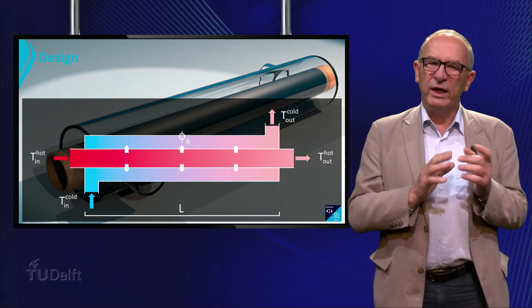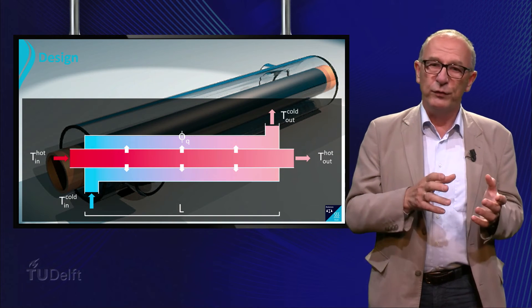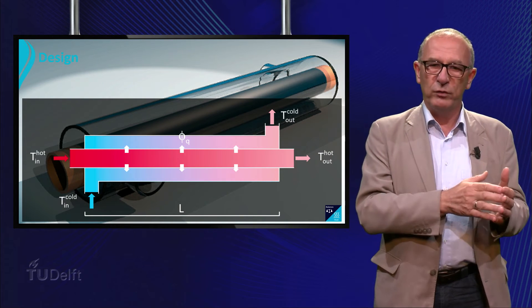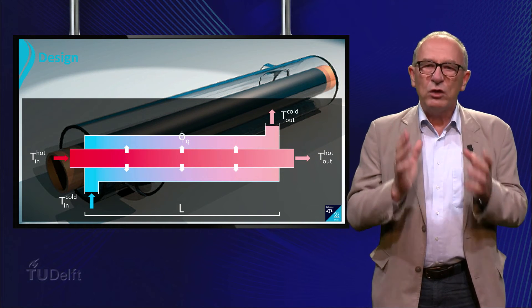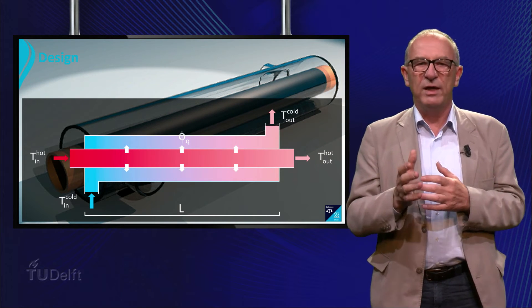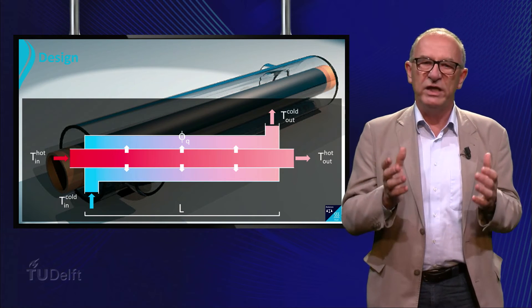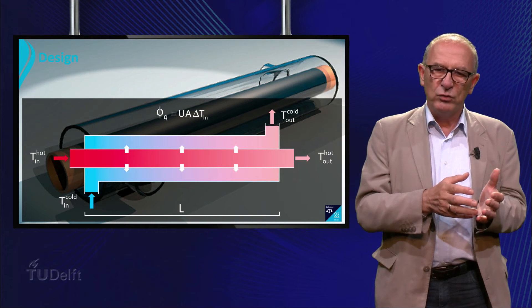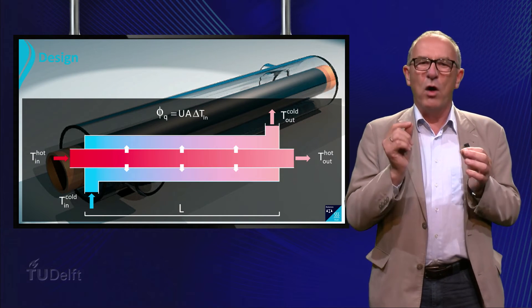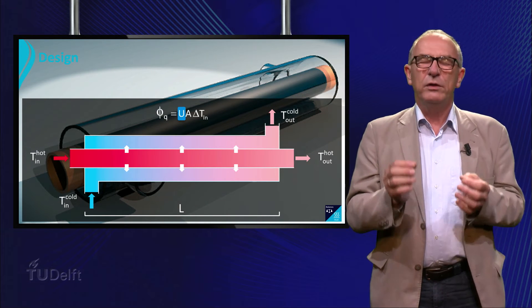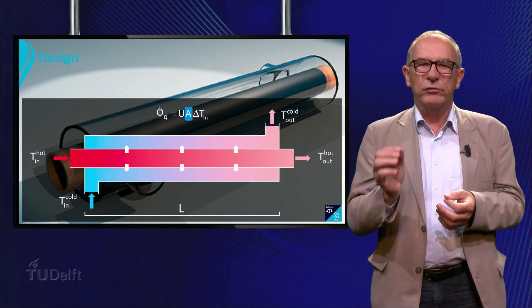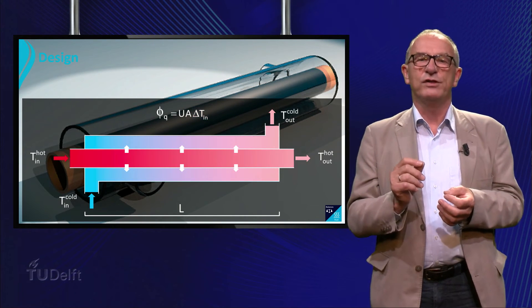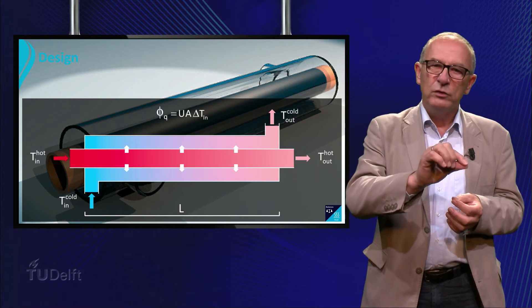In this example, we know the inlet and outlet temperatures of the involved fluids, and as a result we know how much energy is transferred from the hot fluid to the cold fluid. The total heat transfer can be expressed as: the amount of energy phi-Q is the product of the overall heat transfer coefficient U, the surface area A, and the so-called logarithmic mean temperature difference delta TLM.